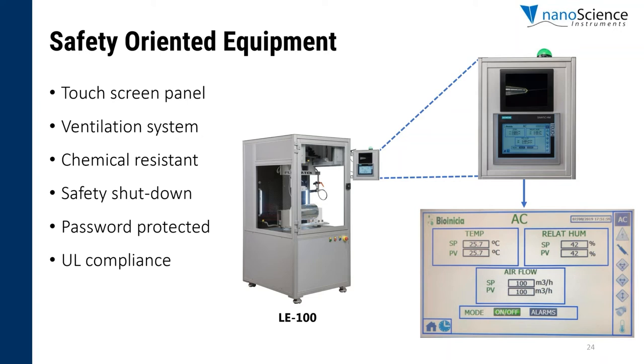Here we see a closer image of a tab that controls temperature, relative humidity, and airflow inside the chamber. So we can control temperature, relative humidity, and airflow. Here you see the SP, set point, and the PV, present value, which is the present value inside the chamber during process development.